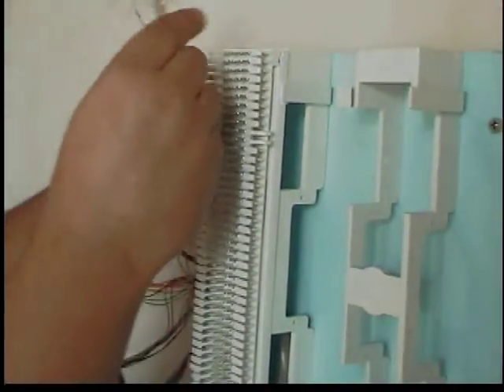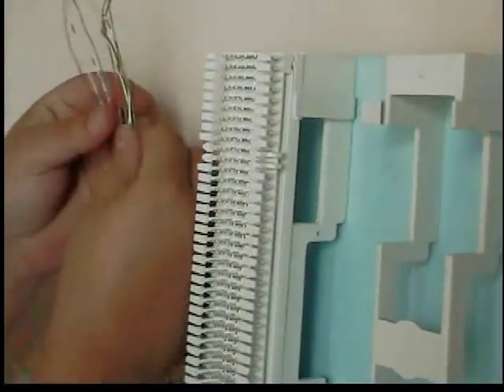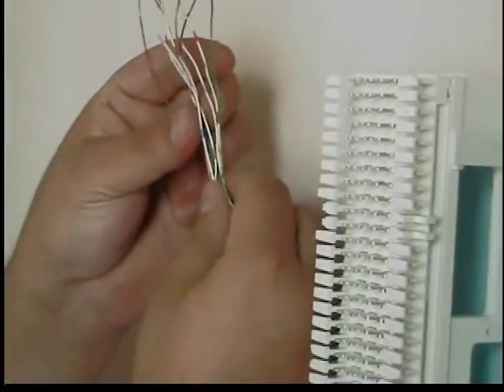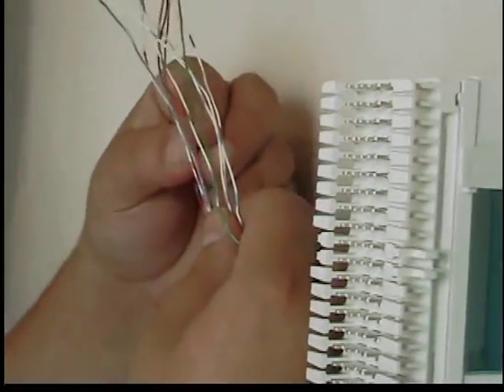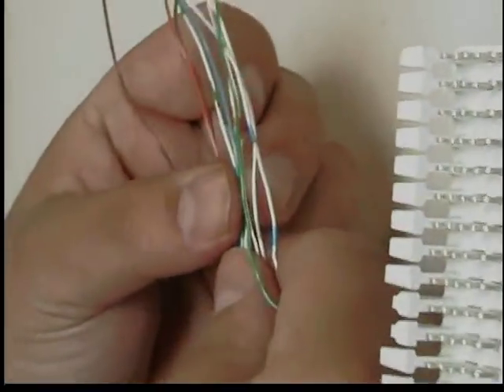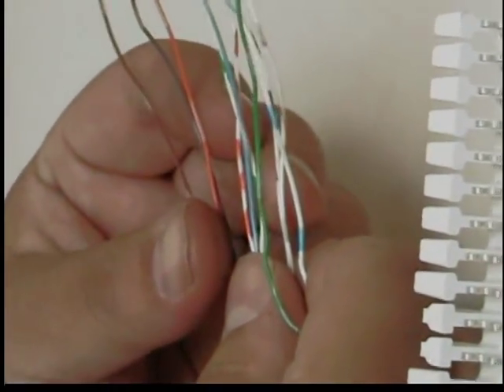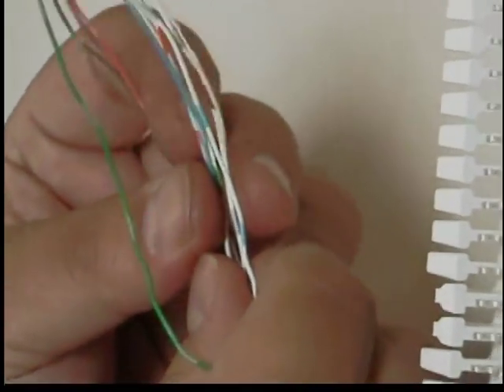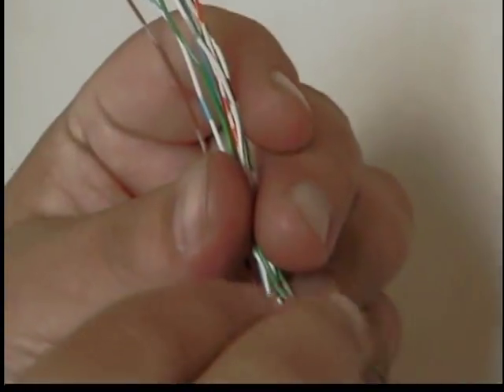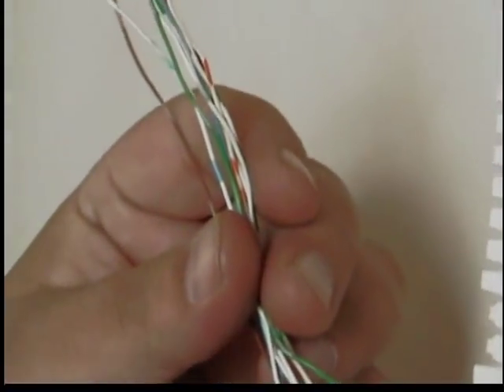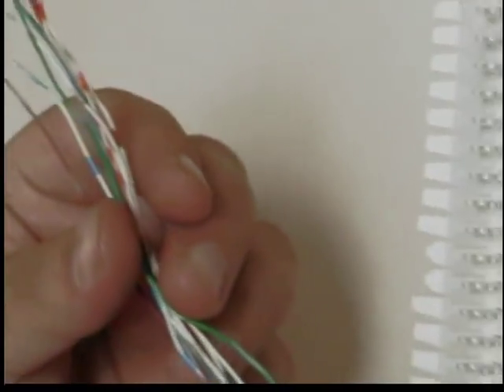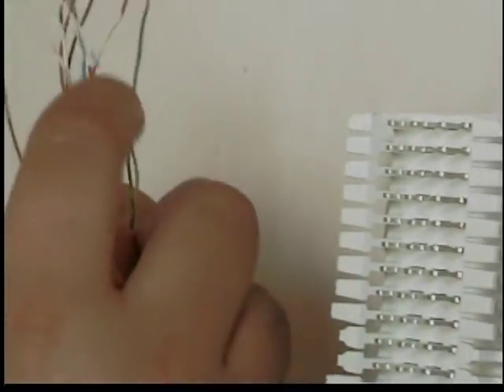Let me separate all these wires. Now, you're going to want to start off, you'll notice there's a few different colors here. Half of the colors have more of the white, and the other half have more of a green, more of a blue, more of an orange, more of a slate, and more of a brown. Now, the white is going to be the primary color, and we're going to start off always with the white on top of the secondary color. So, the first pair is going to be white-blue.